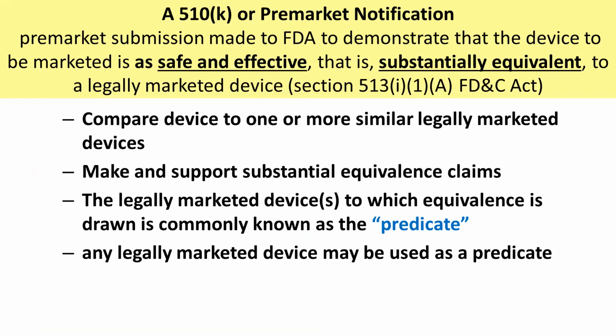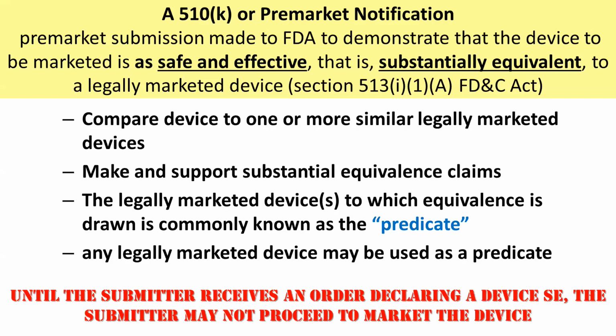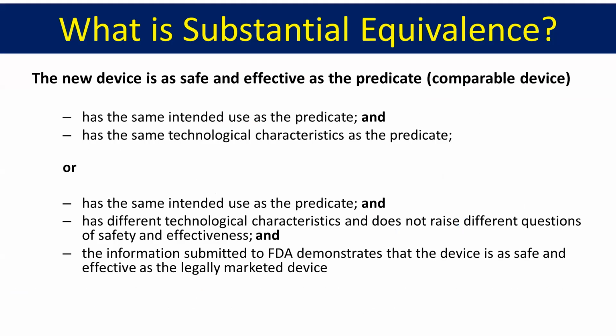So what's interesting about the 510K is that you can say that your device is similar or has equivalence to a substantially equivalent device, which is known as the predicate, and any legally marketed device can be used as the predicate. But until you get your order saying that your device has substantial equivalence, you still can't proceed to market.